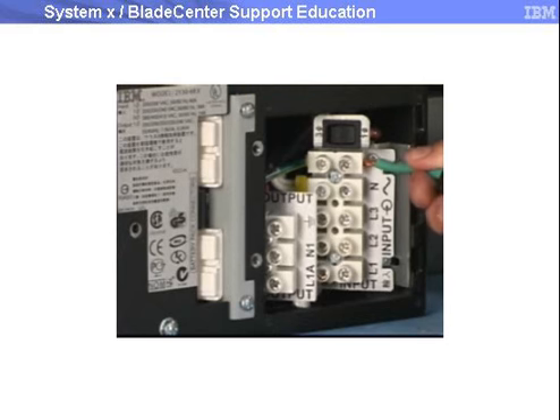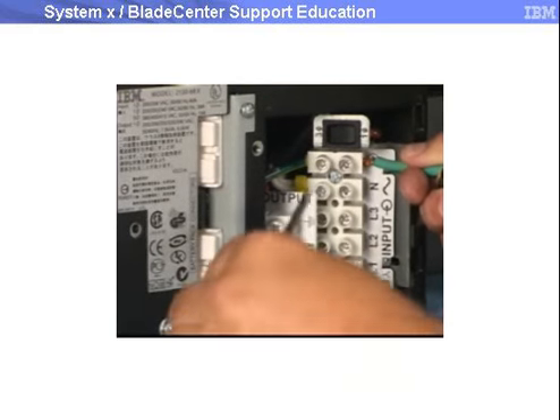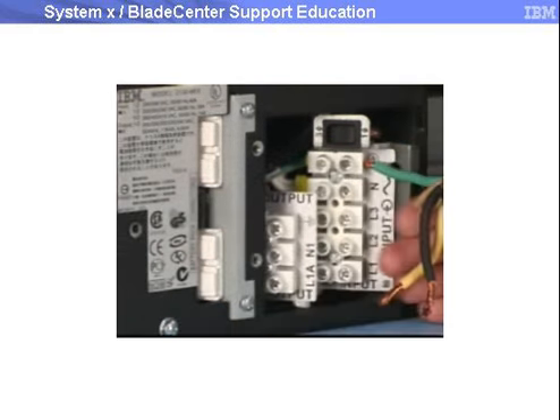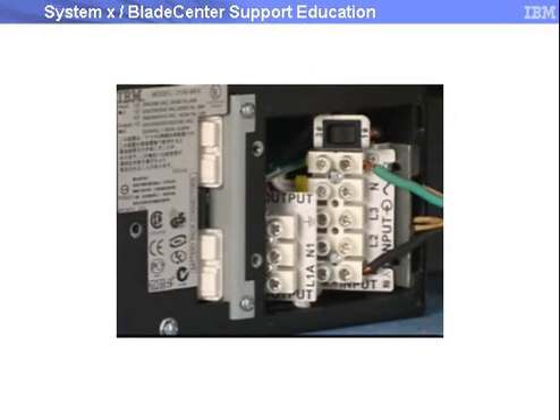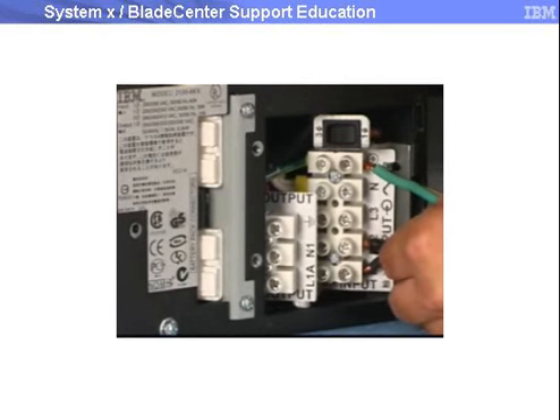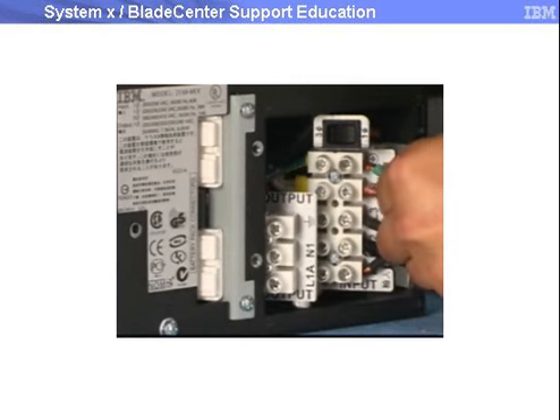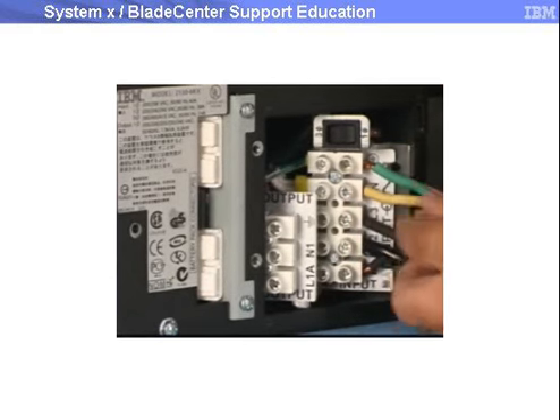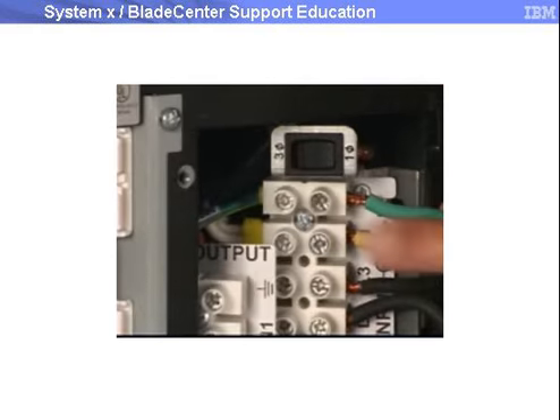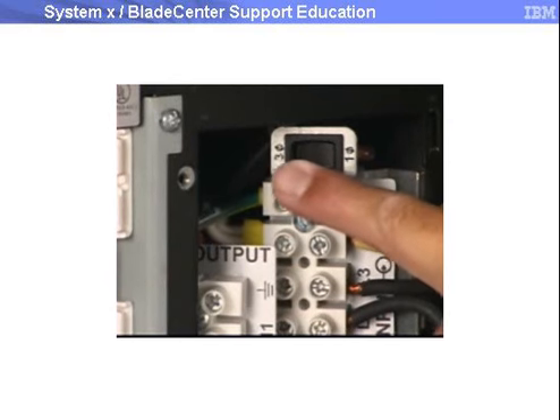Connect the ground wire to the input ground block first. If wiring to a 3-phase supply, connect the L1, L2, L3, and neutral wires to the input terminal blocks at the indicated points. Set the phase selector switch next to the terminal block to 3.